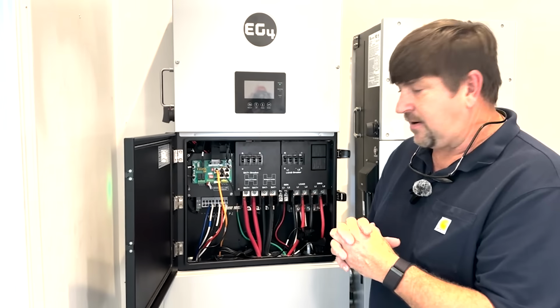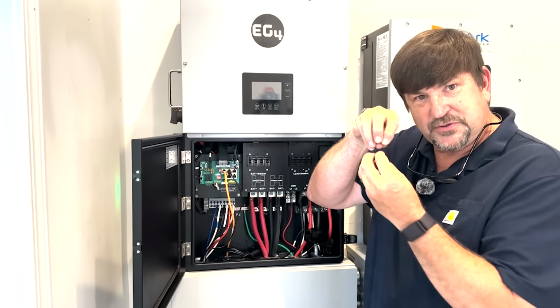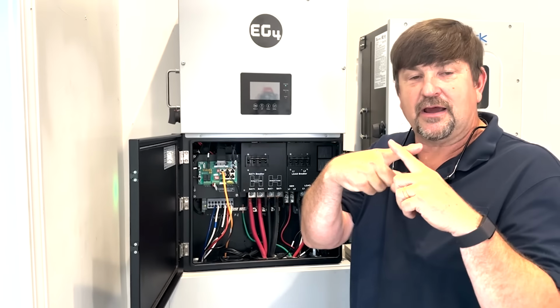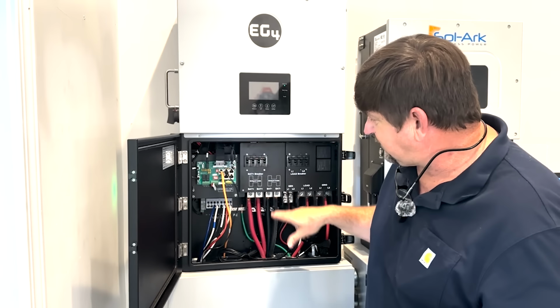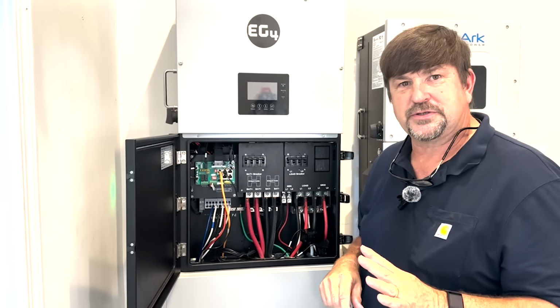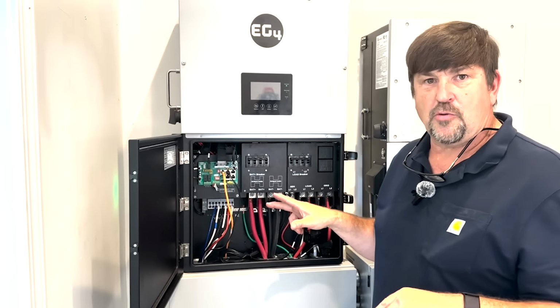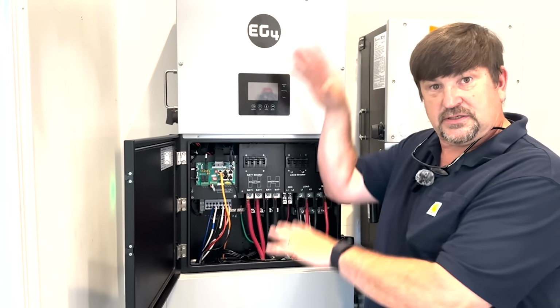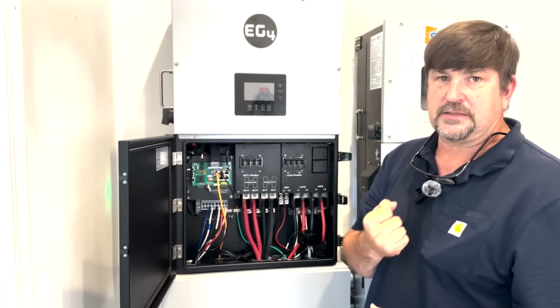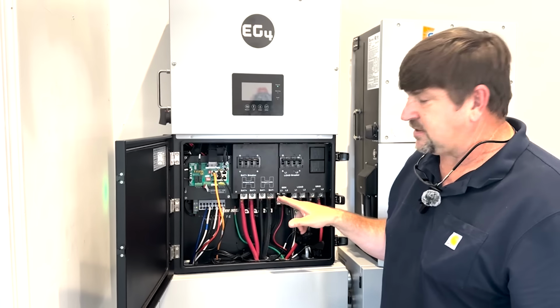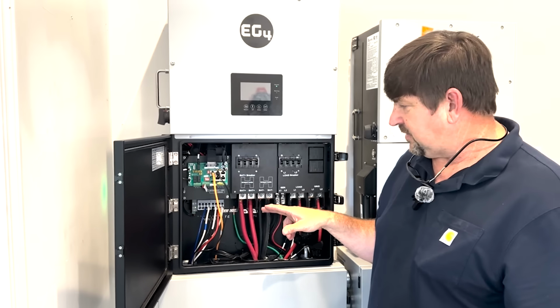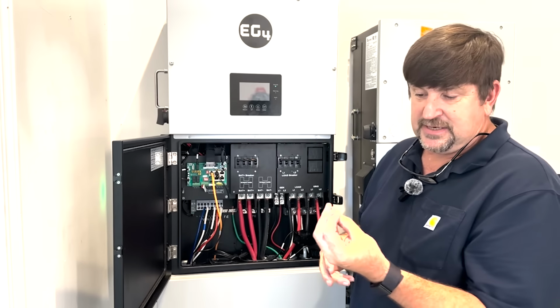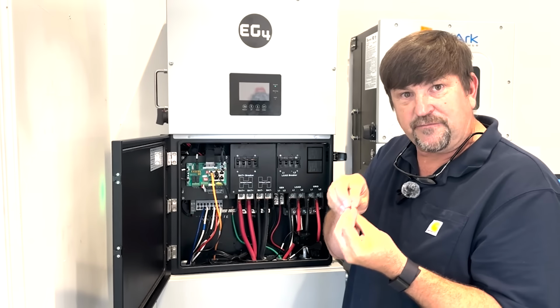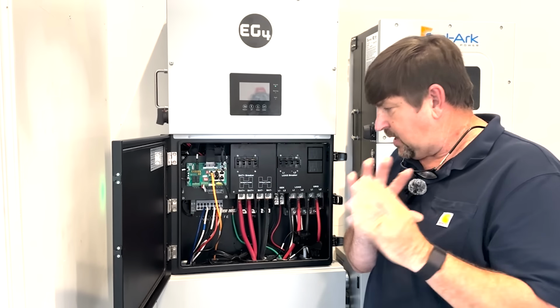Good quality battery cable, it's very difficult to get all those strands put in there. If you've got strands hanging out, they do have some good dividers, so you're probably not going to short circuit. But you definitely want to go back after running this, because it gets hot and cold, so you want to retighten and retorque all these connectors to spec in the manual, because they're going to loosen up. And when you take them back out, they're completely deformed. It's not what you want to do with a battery cable, in my opinion.